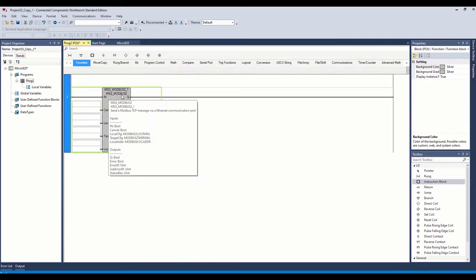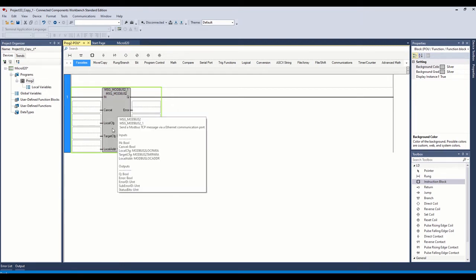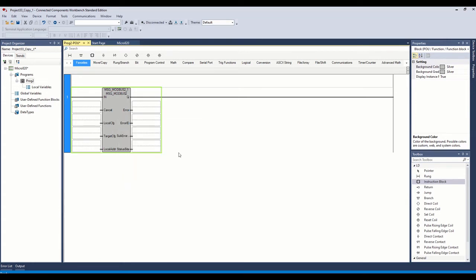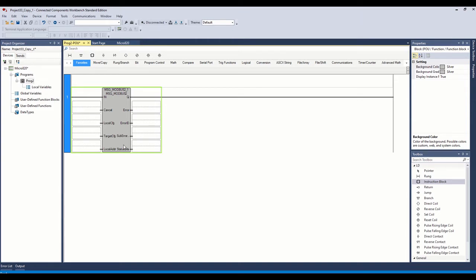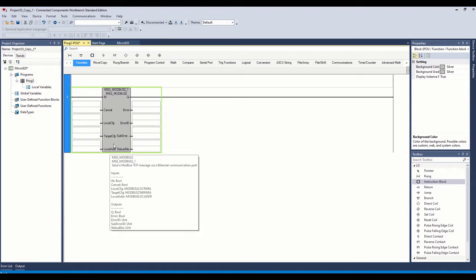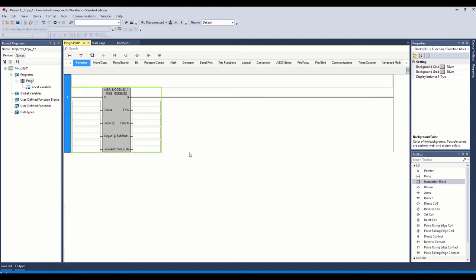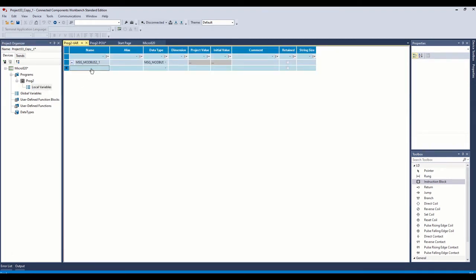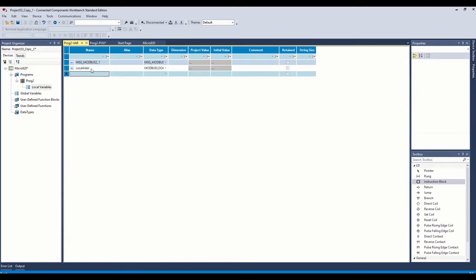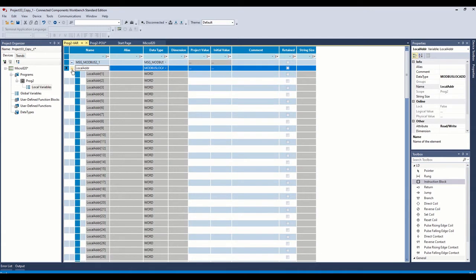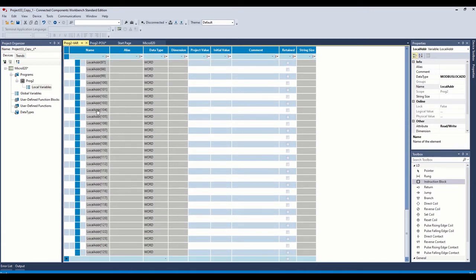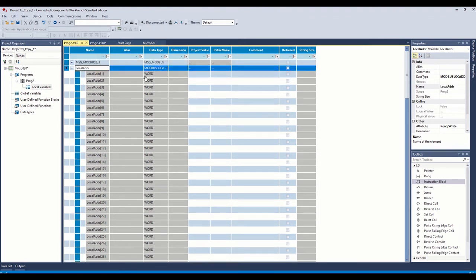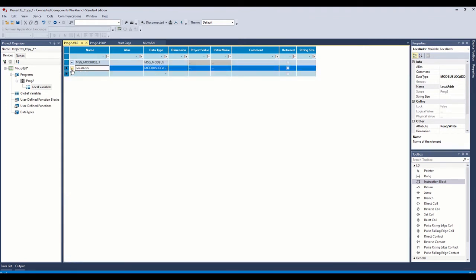And it's called MSG Modbus 2. If you hover over it, it tells you what the tags are that you need. The three that we absolutely need to create in here are these local config, target config, and local address. Those are what configure the message instruction, give it the information it needs, and tells it where to put the information it's going to gather. So let's go back over to our local variables over here on the left. And we're going to go ahead and create these. So the first one will be we'll just go ahead and create our local address. The local address, that's the array of words where we would either map the data that we're going to write out using the instruction or where we're going to put the data we're reading in.